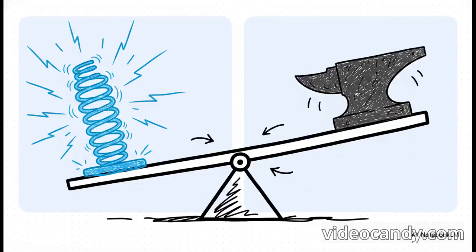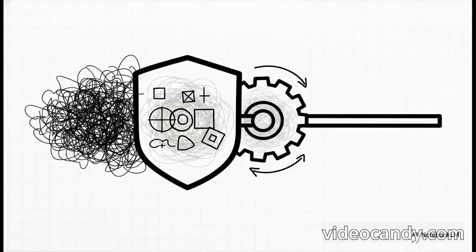Control engineers face a really brutal fundamental compromise here. Do you want a high-gain, incredibly rigid system that rejects disturbances instantly but shakes itself to pieces? Or do you want a low-gain, heavily damped system that runs incredibly smoothly but completely loses its ultra-high-speed precision? Standard PI tuning effectively forces you to pick a point on this sliding scale of compromise. This is where Advanced Position Control, or APC, steps in to save the day.